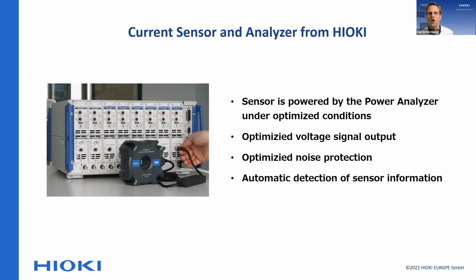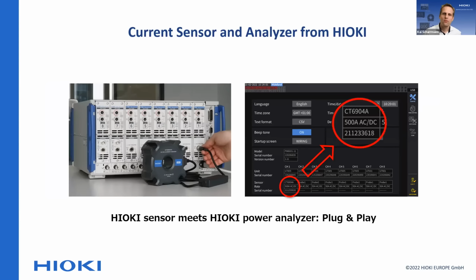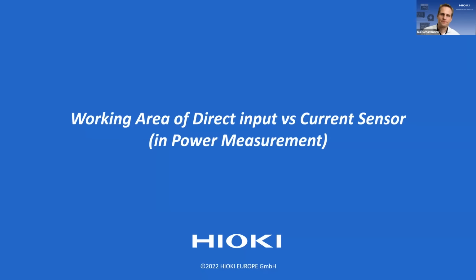Depending on the power analyzer you use, there's even automatic detection of the sensor information. If you plug a current sensor from Hioki into a Hioki power analyzer, it reads out relevant information from the sensor, such as the output ratio, which is one of the most important things. It also reads out phase errors of the current sensor, but we'll talk about that in a minute.